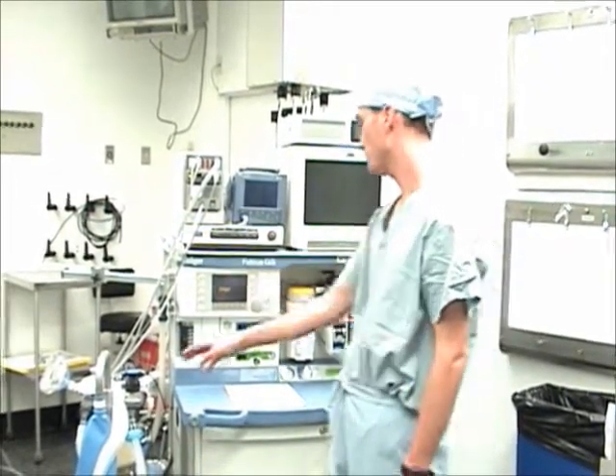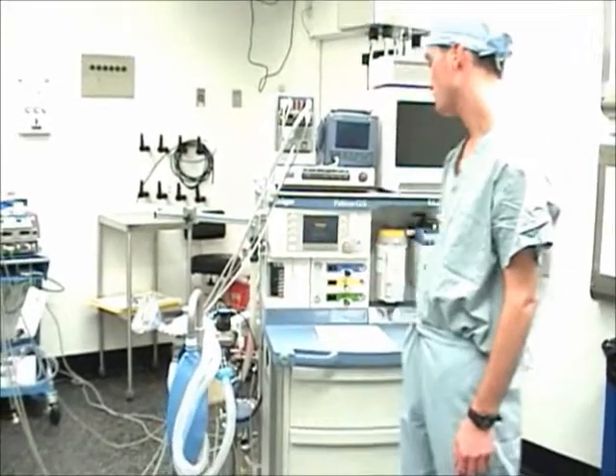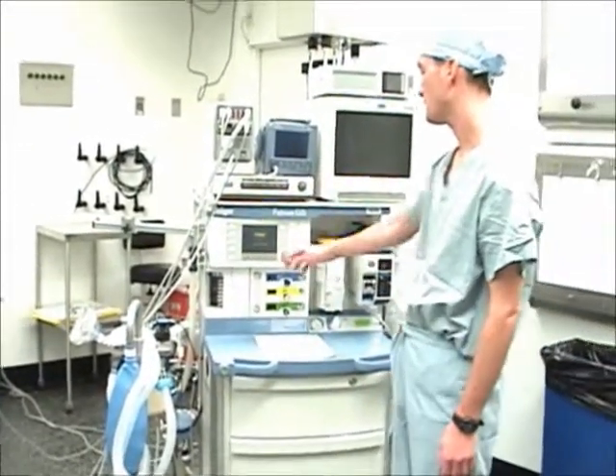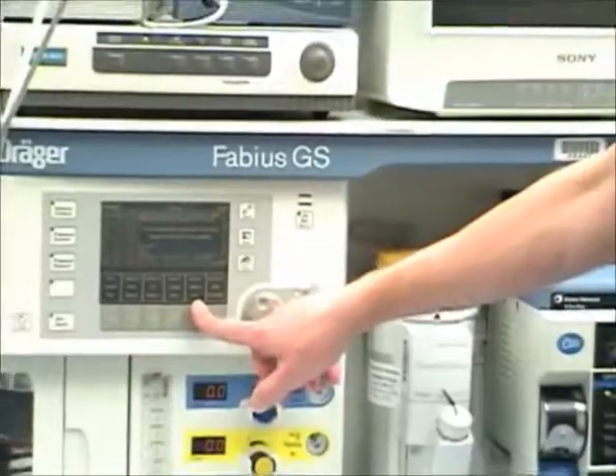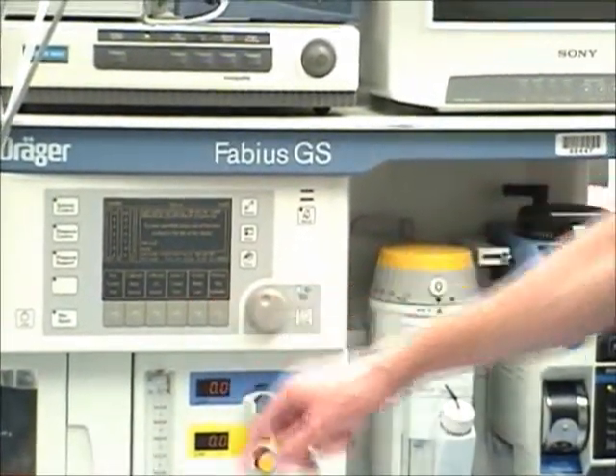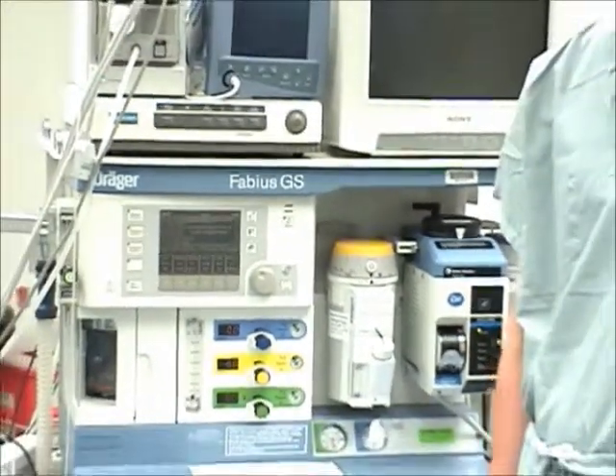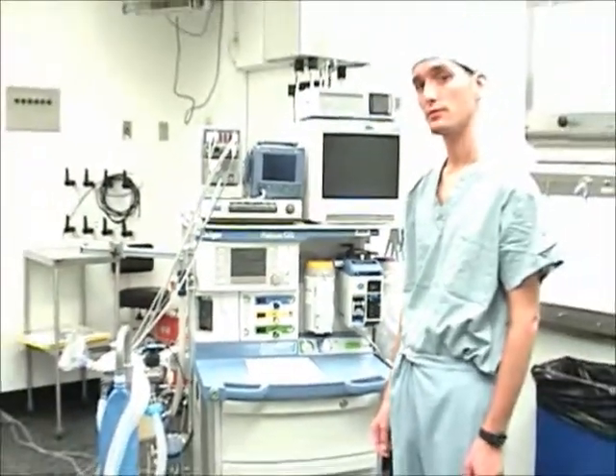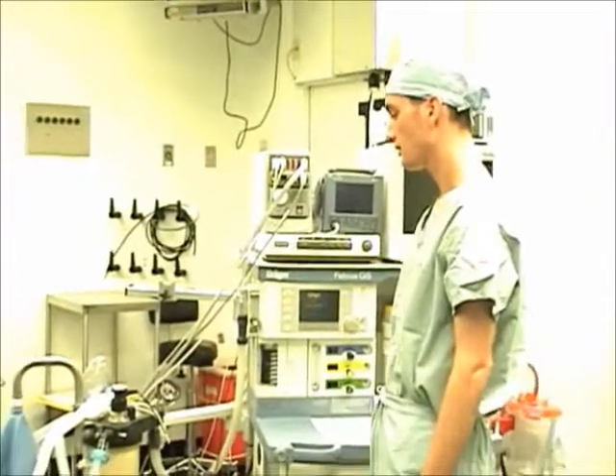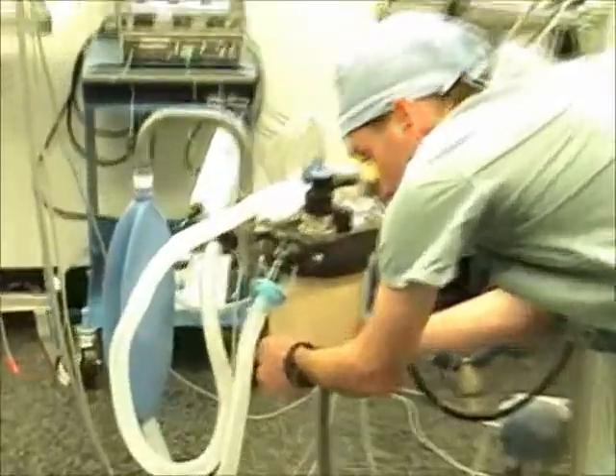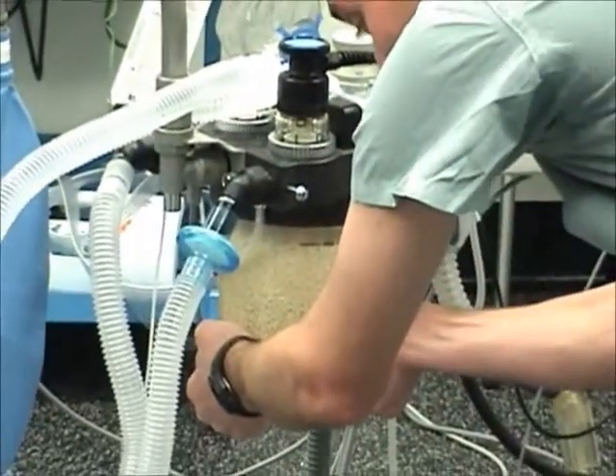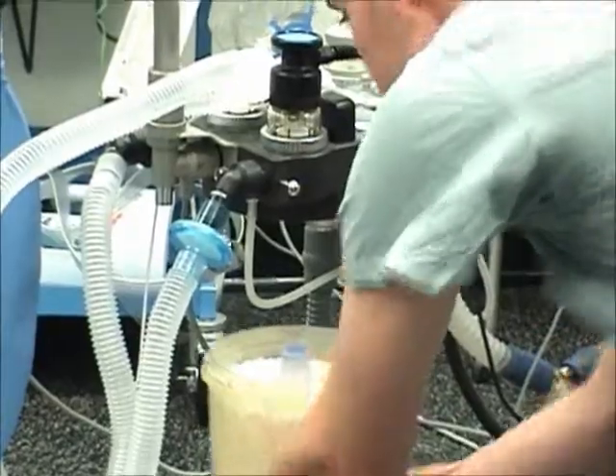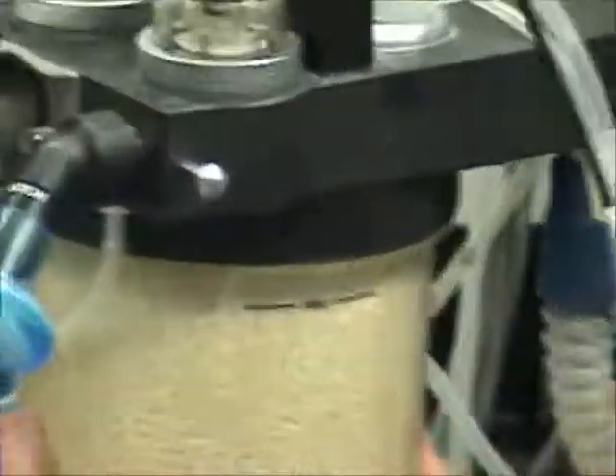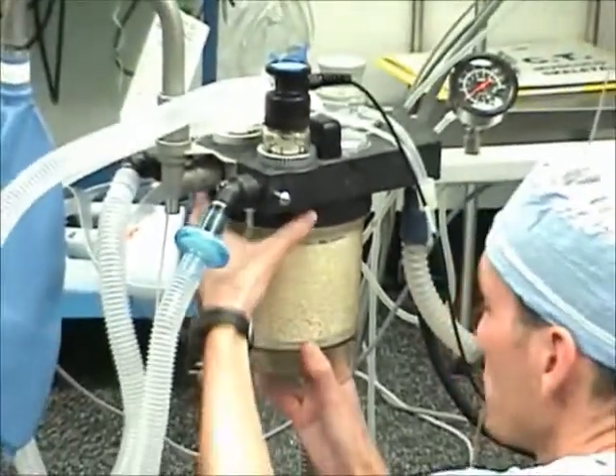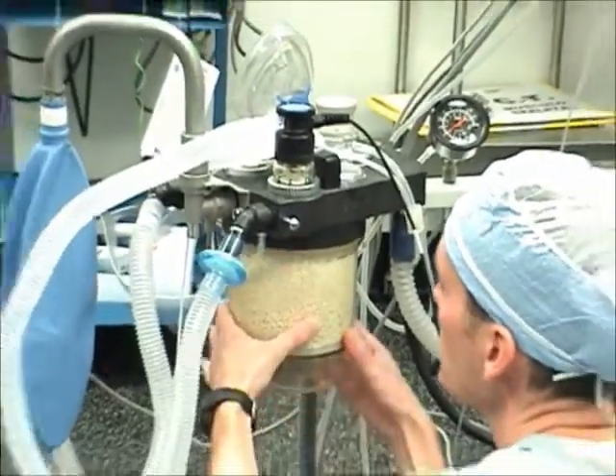If the same circuit type is used throughout the day, only a manual leak test is required. A leak compliance test, however, must be completed each time there is a change in circuit type. For example, when a pediatric or an expandable circuit is used. To access the carbon dioxide absorbent canister, grab the bottom and turn clockwise. Reinsert, align with the threads, turn counterclockwise.